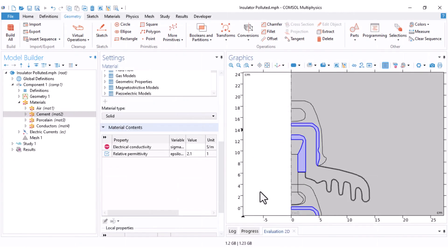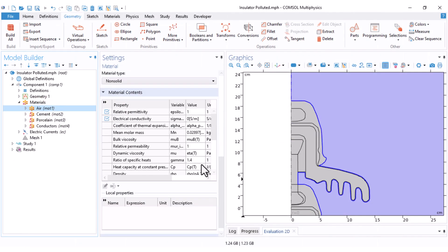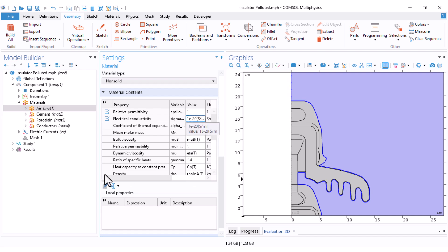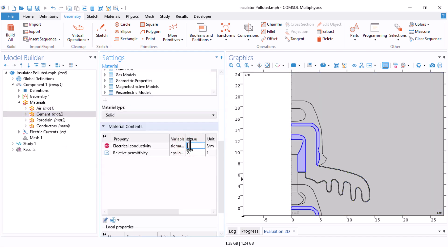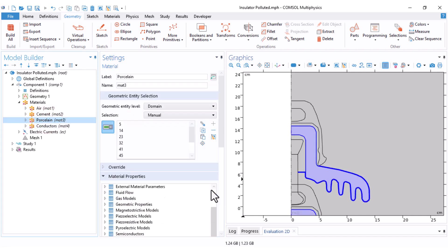Air conductivity should be near zero. Clicking on Air shows it is already set to zero, but this can be tricky because sometimes the model does not converge due to this zero value. To prevent that, I prefer to define it as a very small value like 10 to the minus 20 — much better than zero and it prevents convergence problems. I then come under Cement and set its conductivity, and then Porcelain.